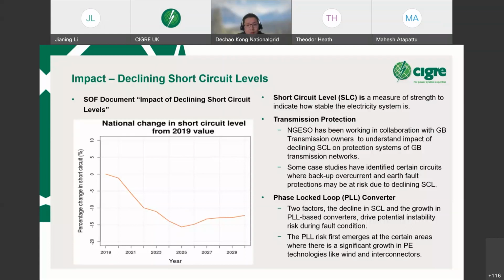Protection systems are designed to have a very high degree of reliability, but they depend on the short circuit level being high enough to trigger a protection relay. It means that if you don't have a high short circuit level, it will potentially trigger mal-operation or no operation of the transmission protection. So National Grid ESO have been working closely with other TOs to understand the impact of the decline in short circuit level on protection systems.